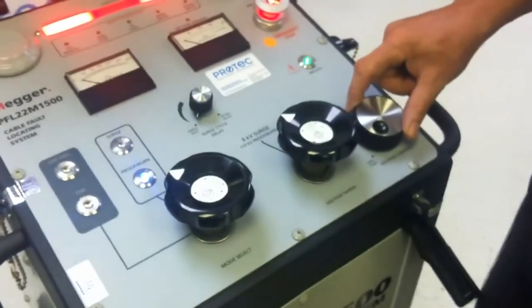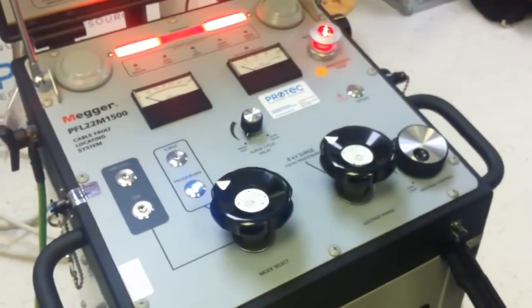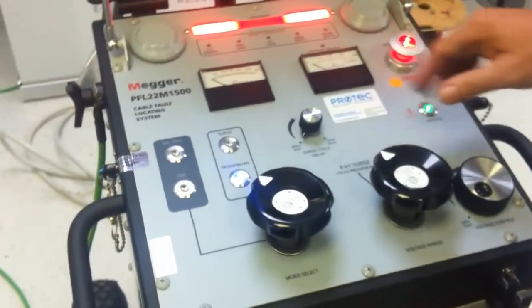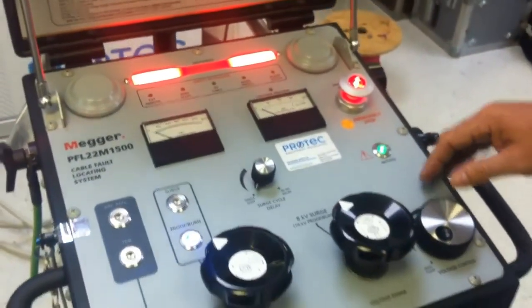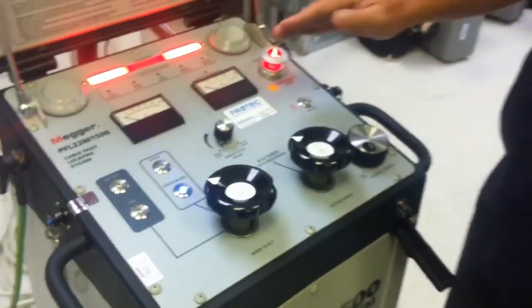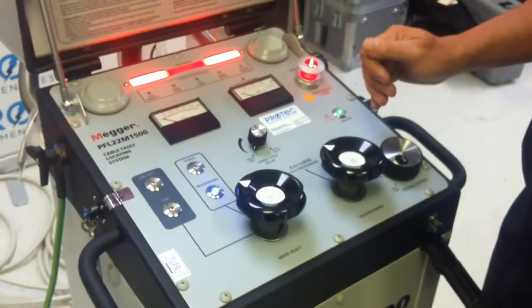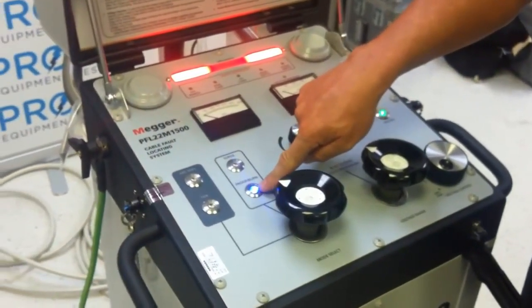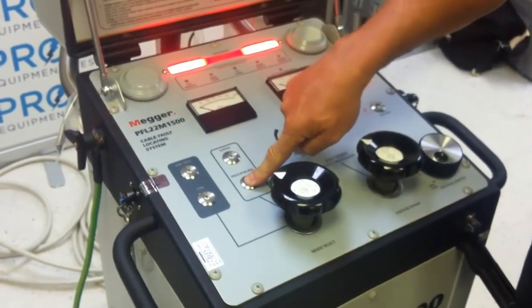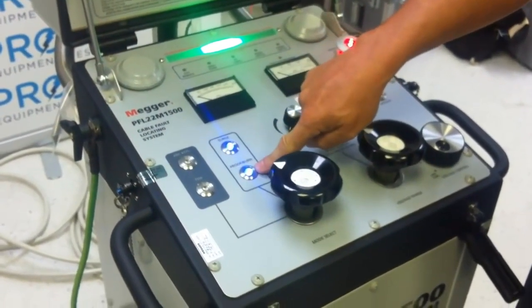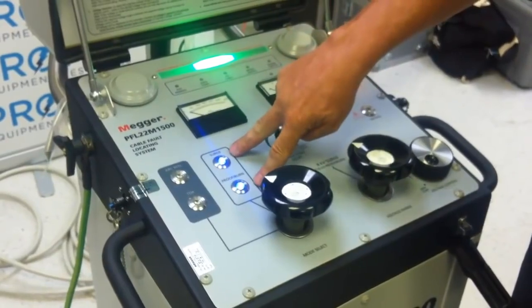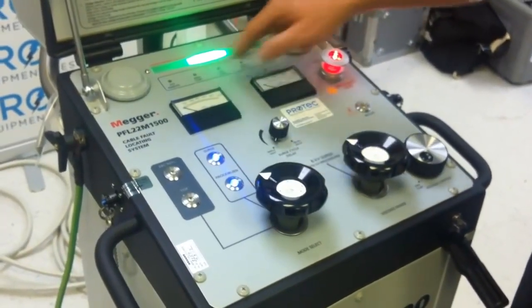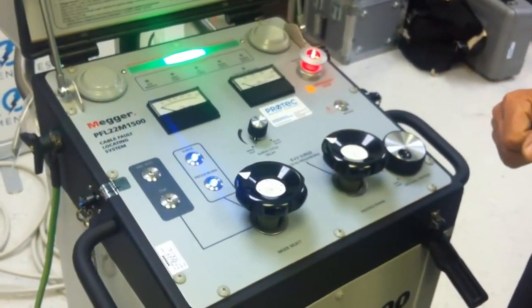I'll bring my voltage back to 0. I know that my spark gap is flashing over at approximately a 5,000 volt level. At this point, to end the test and to go back into a safe ground condition, I merely repress my proof burn, I disengage my high voltage, and I go back to a safe grounded state.